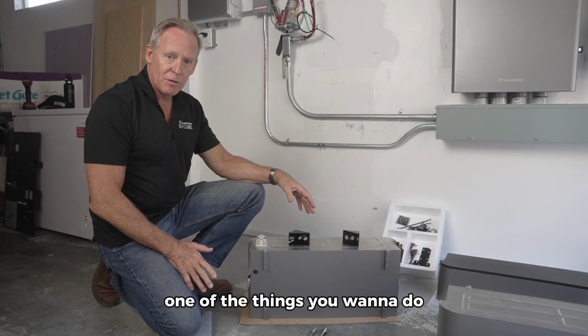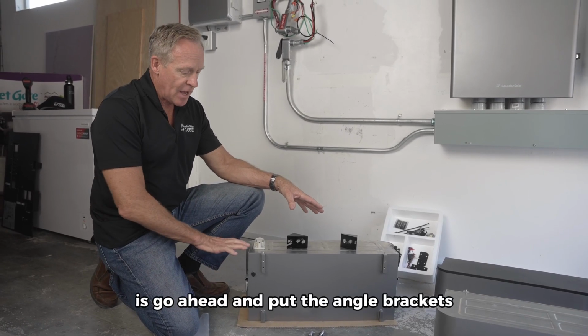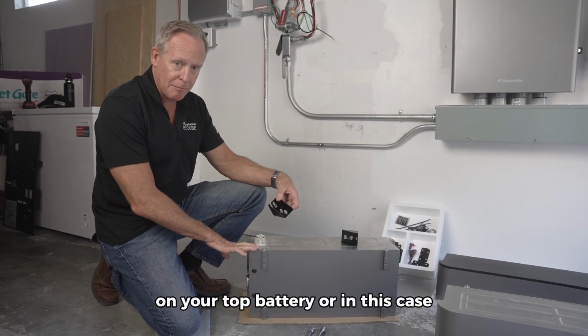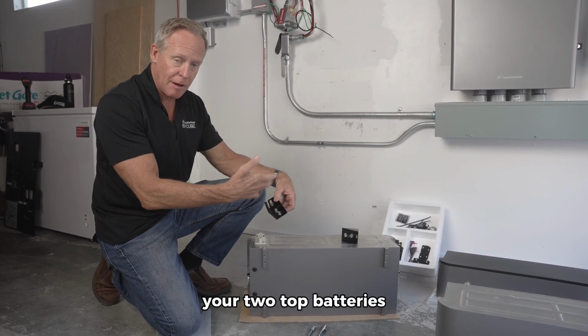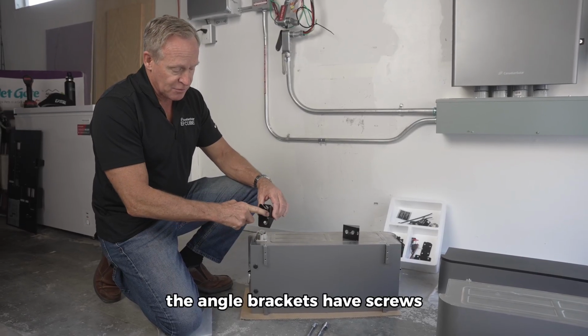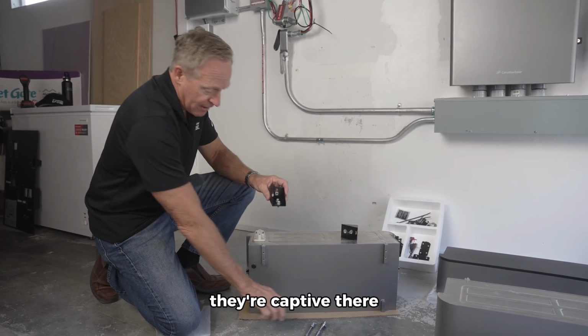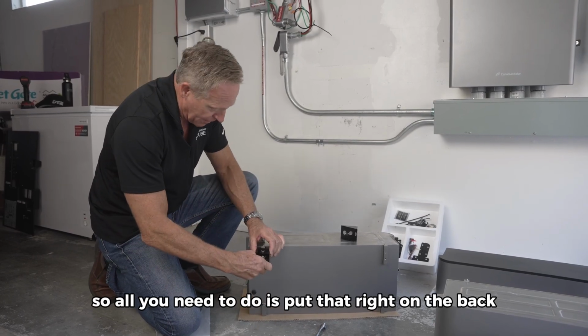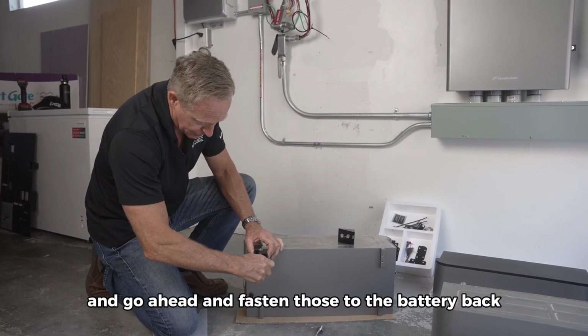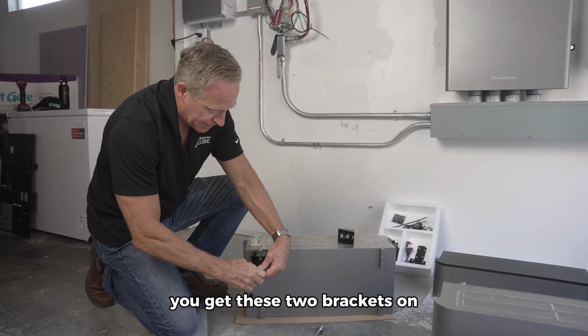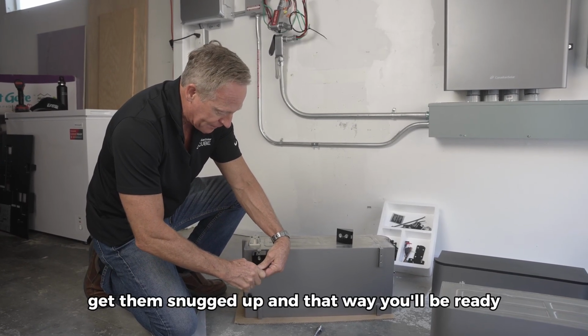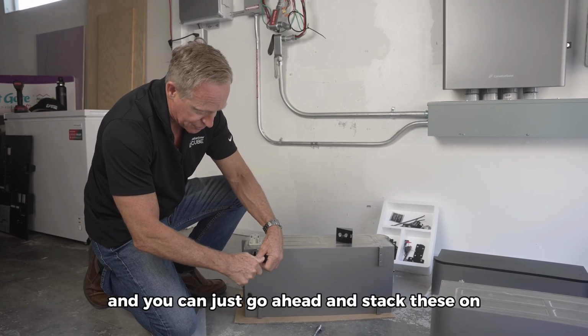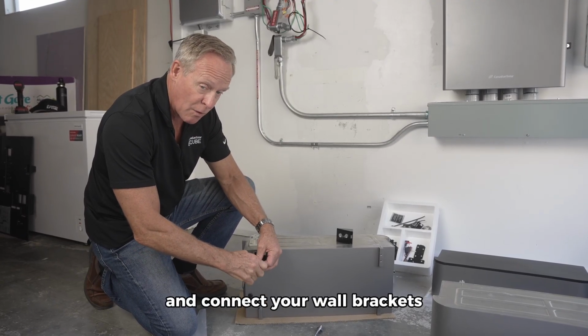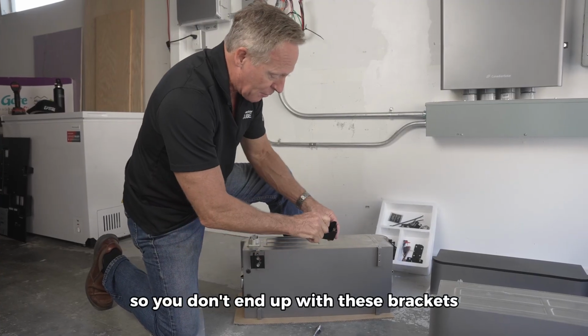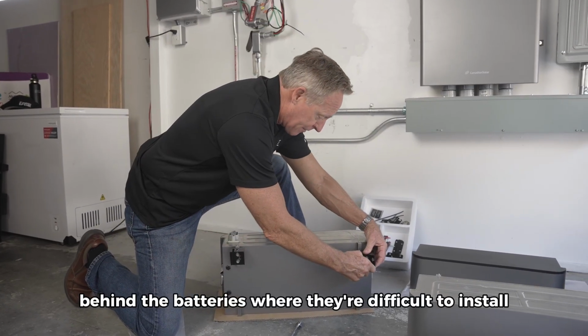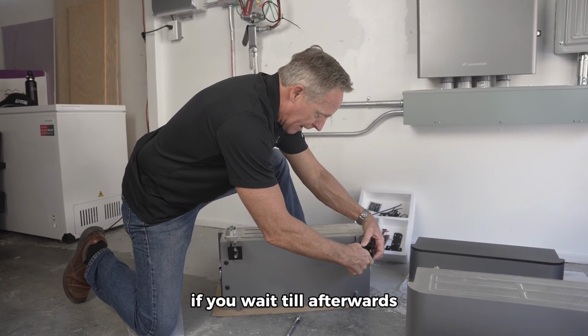One of the things you want to do before you start stacking the batteries is put the angle brackets on your top battery, or in this case your 2 top batteries. The angle brackets have screws that are already attached and captive, so all you need to do is put that right on the back and fasten those to the battery back. Get these 2 brackets on, get them snugged up, and that way you'll be ready to stack these on and connect your wall brackets, so you don't end up with these brackets behind the batteries where they're difficult to install if you wait till afterwards.